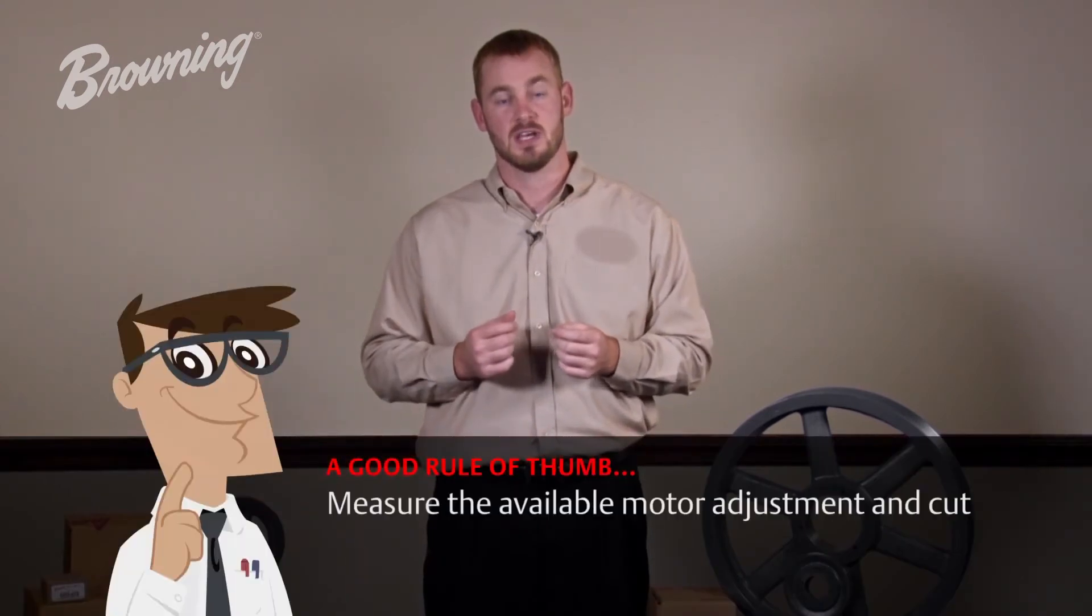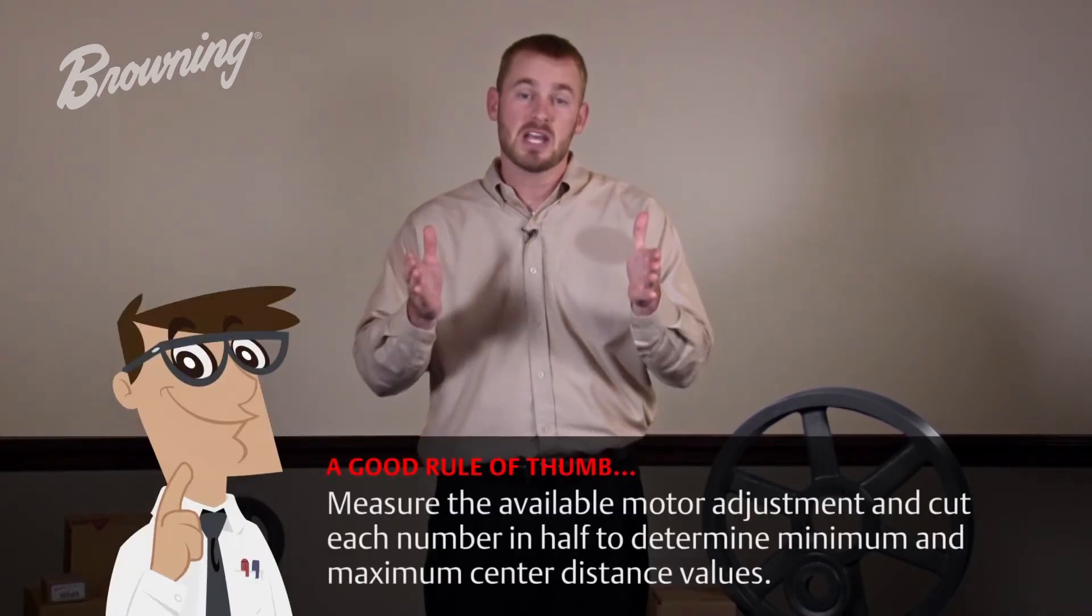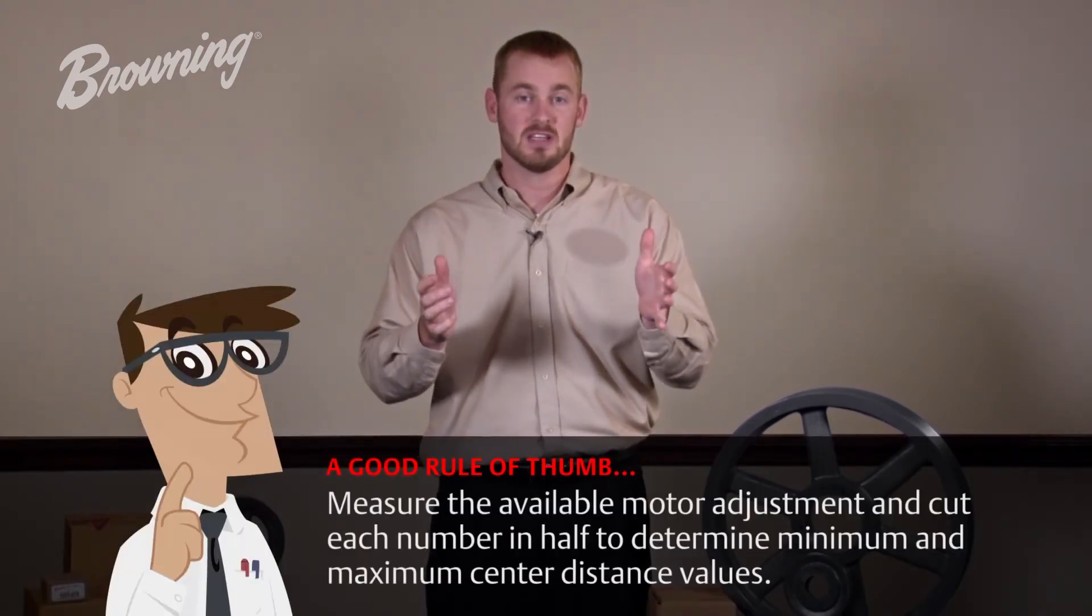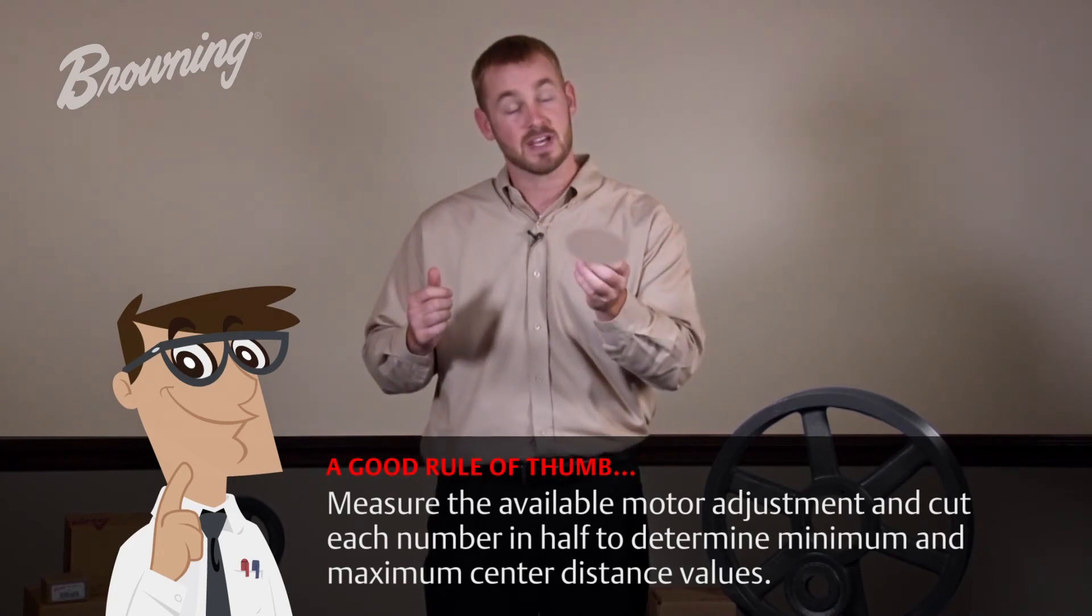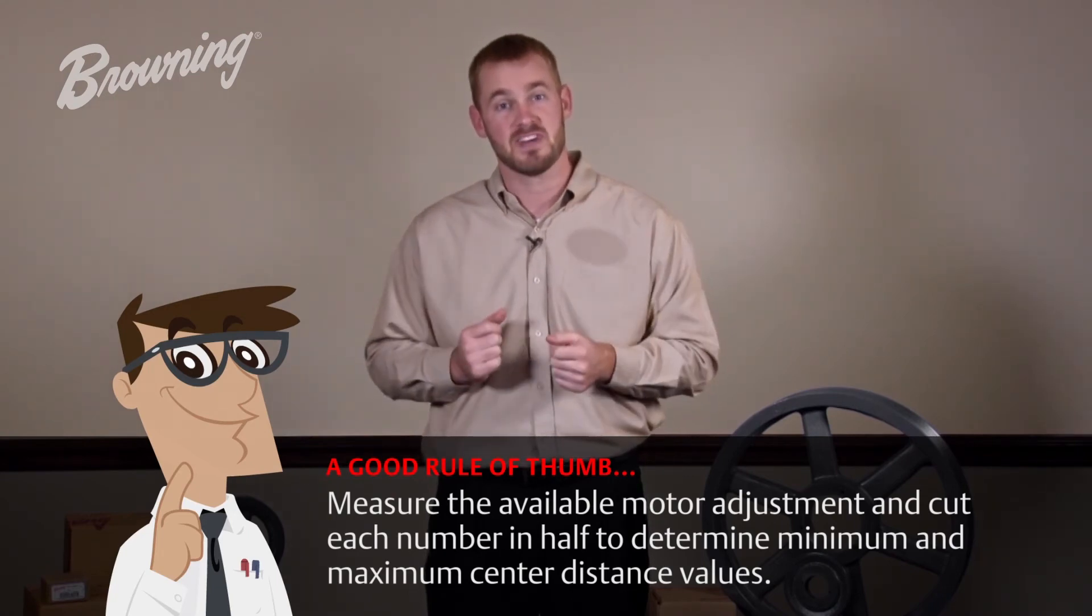Please do your best when measuring minimum and maximum center distance. A good rule of thumb is to measure the available motor adjustment and cut each number in half to determine minimum and maximum values. Keep in mind, for Browning to select a retrofit solution, we need a minimum of 2 inches in center distance variation.